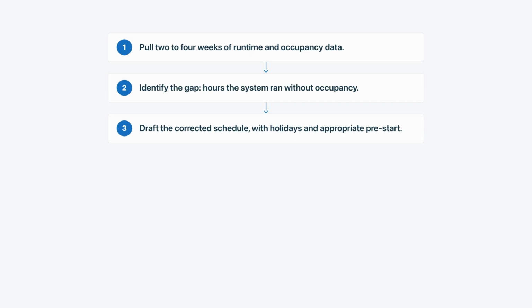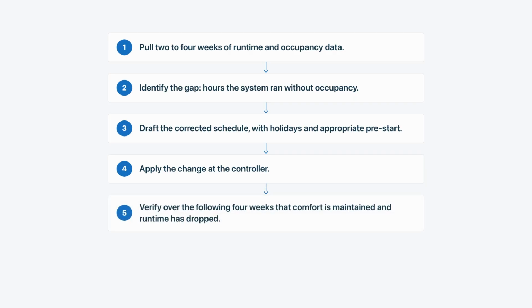And then step 4 is to apply those changes at your controller. For a standalone thermostat, that's typically going to be your programming interface, which may take you 10 or 15 minutes. Step 5, and this is the one that people skip, is to verify this. Watch the next 4 weeks. Temperatures should still hit the set point during occupied hours. Nobody should be complaining about comfort, but your runtime should be down, proportional to the hours that you've removed. If all of those are true, the correction's good and will keep paying you back every year until the schedule changes again. And if something's off, you'll have the data to see exactly what and adjust.